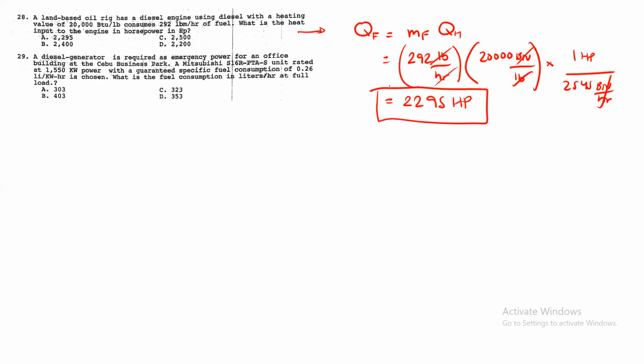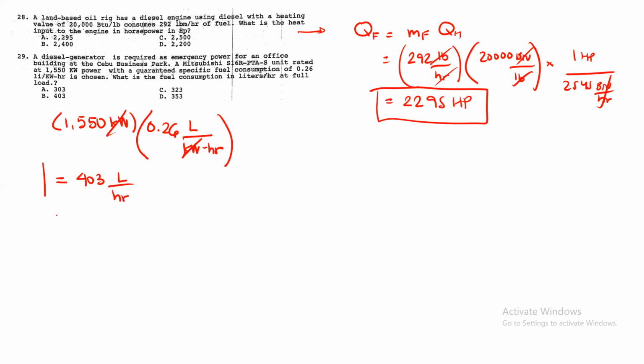The next, number 29. So, dito, hinahanap sa problem na to, what is the fuel consumption in liters per hour at full load? Hinahanap kasi dito yung fuel consumption, so volume flow rate. Medyo madali lang to, no? Unit analysis lang din. So, 1,550 kilowatts, i-multiply mo lang siya ng 0.26 na fuel consumption, liters per kilowatt hour. Kahit hindi mo alam yung formula, basta unit analysis lang. So, 403 liters per hour. The answer is letter B.